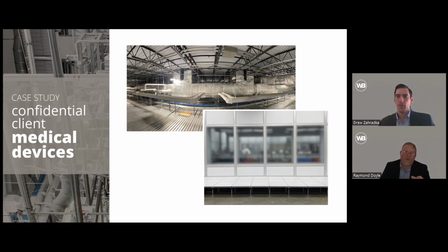So it gives you the opportunity, if you challenge your science and your assembly process, which can be up on a platform or up on a table, to be the clean environment, not the level at the floor where the particle counter really doesn't matter because it's not directly in contact with the actual medical device or that phase of the assembly of that device, which is the other part. You've got to make sure you meet the standards you're building to. But we were able to save them a lot of money by challenging their own guidelines and pushing them in a direction that gave them a lot of capital to be able to use towards other equipment that they needed.